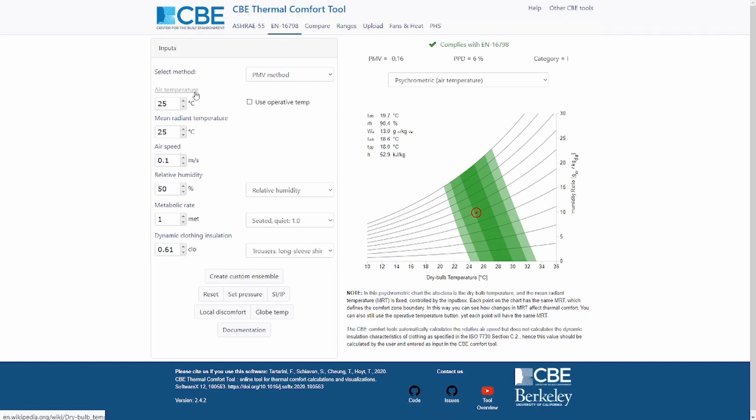For instance, air temperature, mean radiant temperature, and air speed are generally the average value measured at three different heights, selected based on the posture of the occupants. If the person is sitting, the heights are 0.1, 0.6, and 1.1 meters. If the person is standing, the heights are 0.1, 1.1, and 1.7 meters.